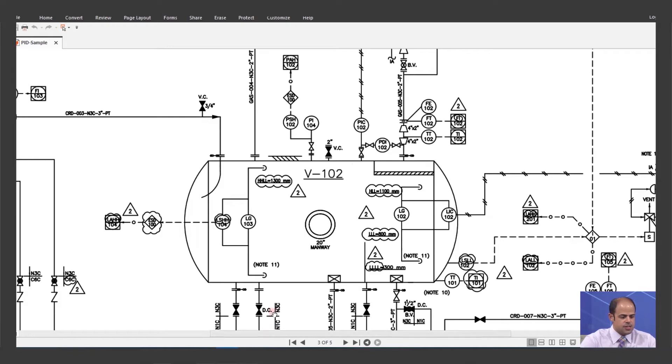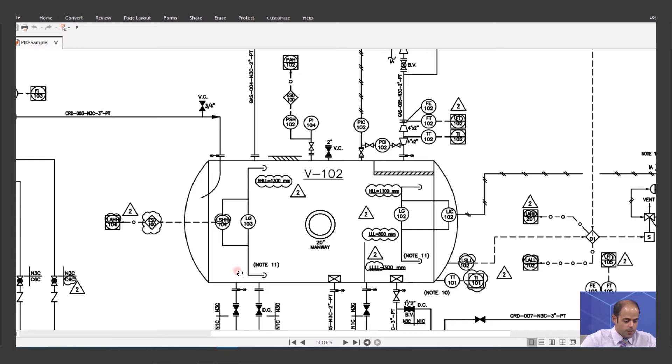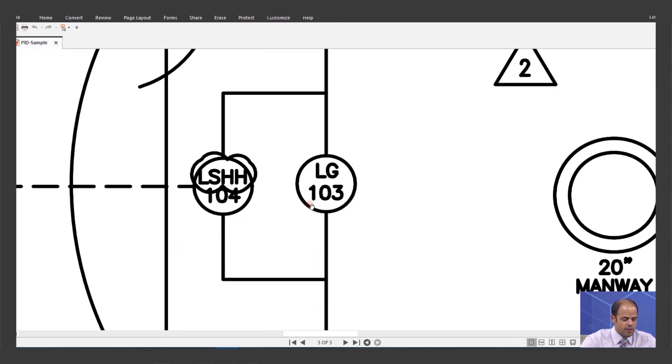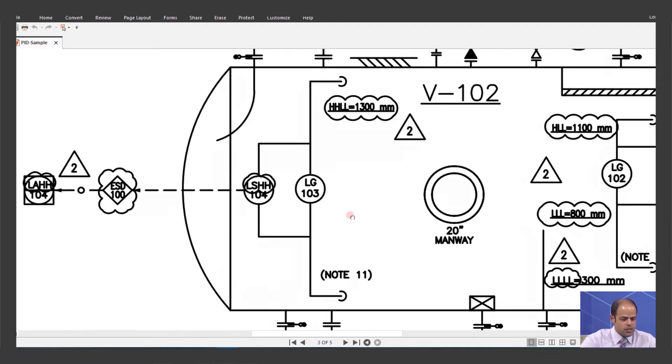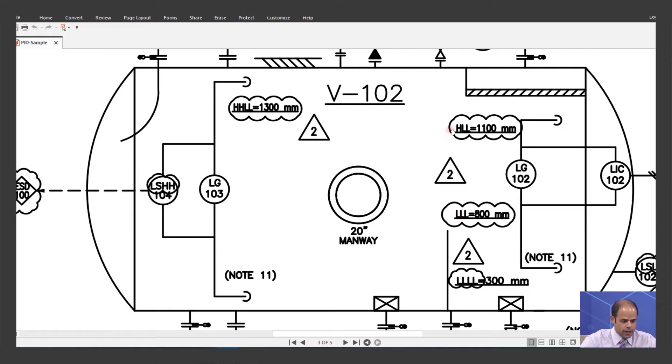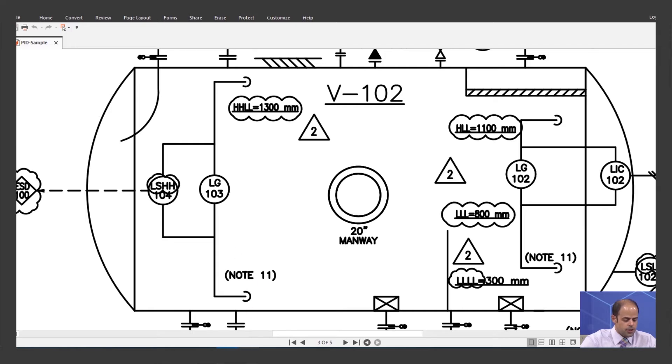As you can see in this data sheet, in this P&ID, I have a drum. The vessel number is 102. And as you can see here, we have a sight glass with a tag of level gauge 103. Based on the points related for low-low, low, high, and high-high, I want to teach you what's the suitable level gauge that you can choose here.